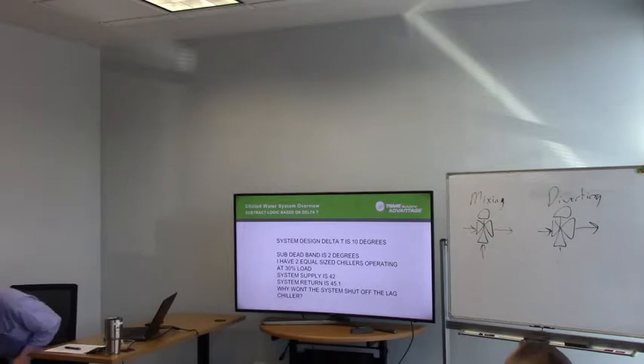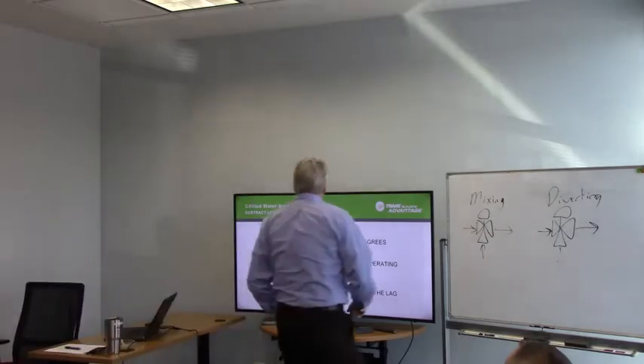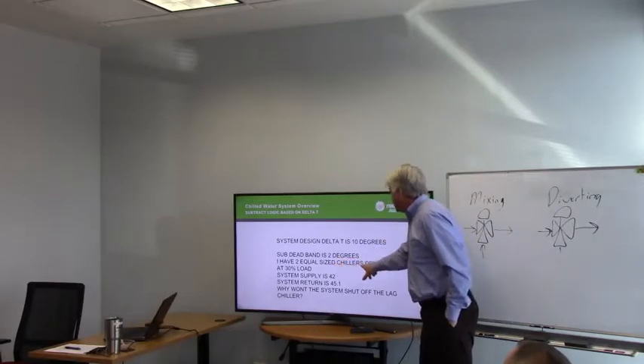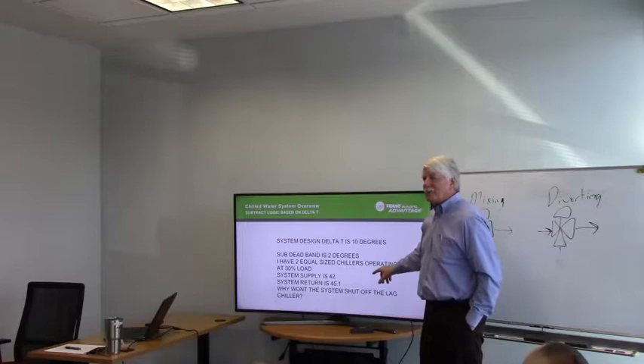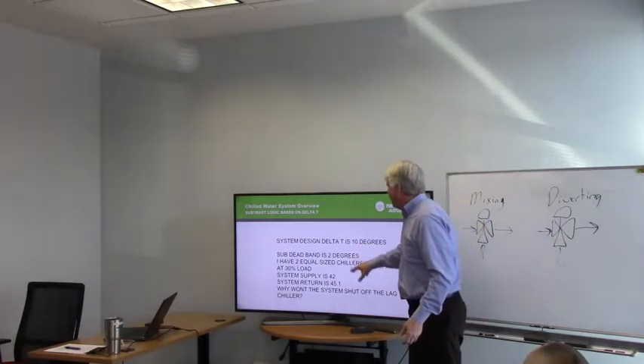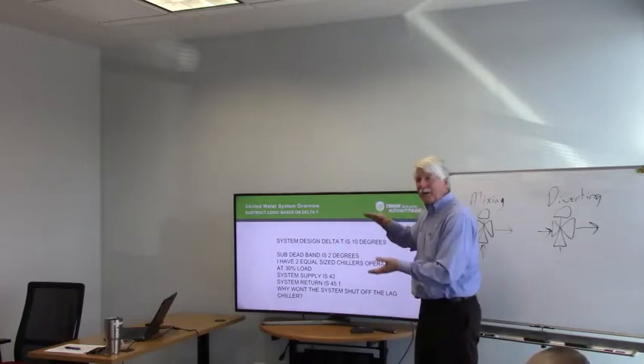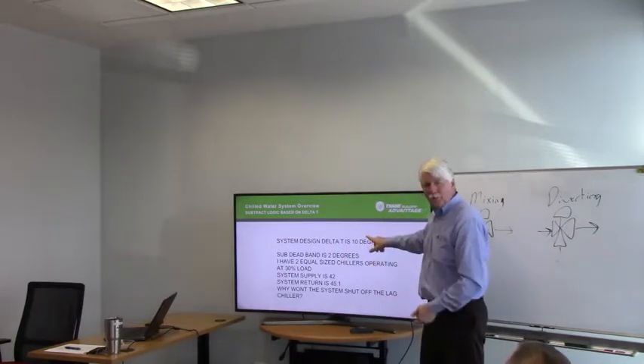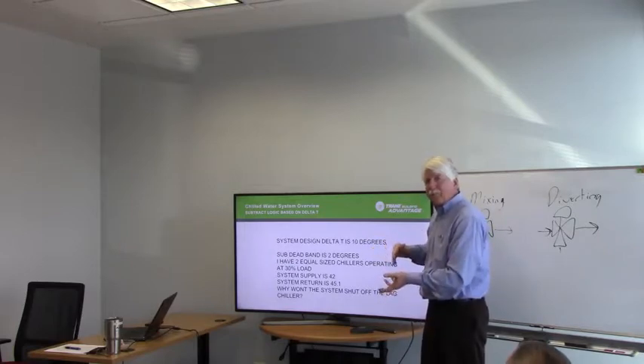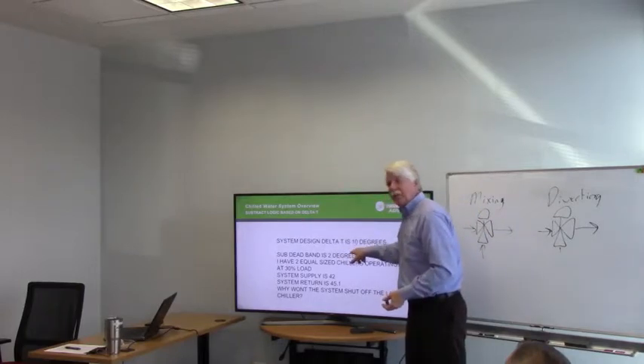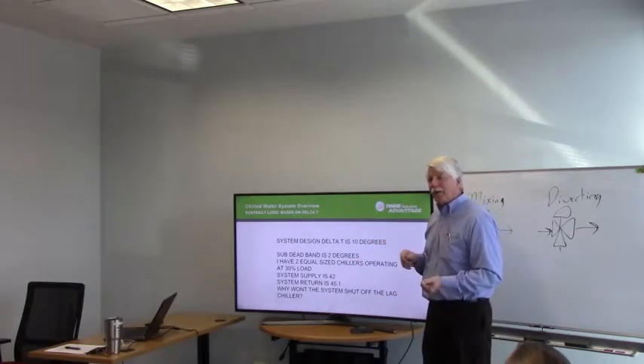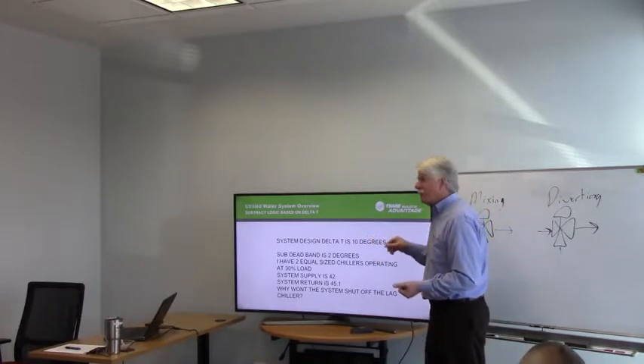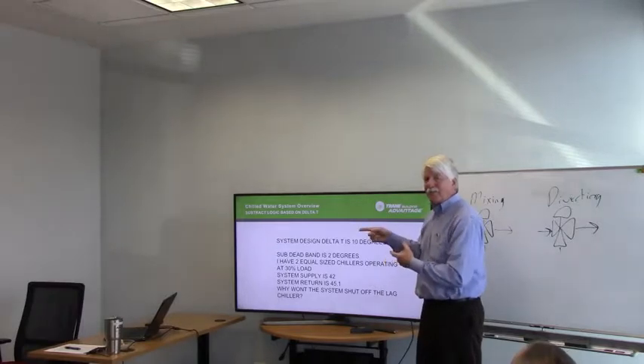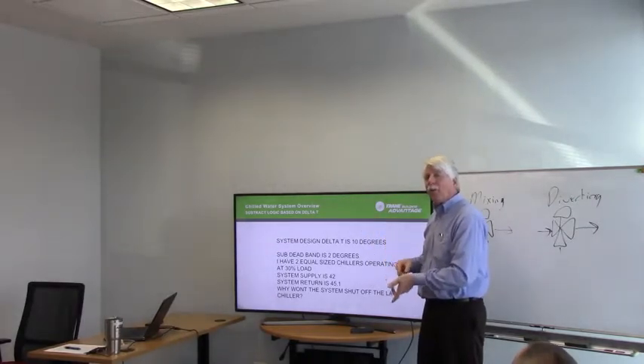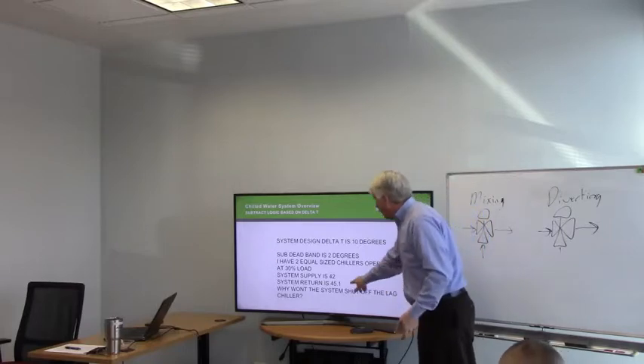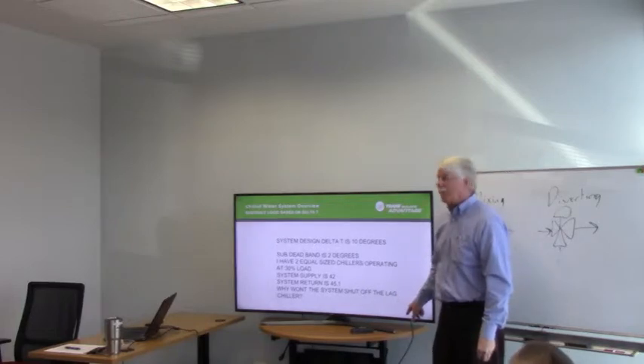The way that chiller plant control works is, first of all, it says I have equal size chillers. So that means theoretically, each chiller can do, of the total system work, 5 degrees worth of work. Because if 2 chillers are doing 10 degrees, 1 chiller can do 5 degrees. And we told it has a 2-degree deadband. Well, if 1 chiller can do 5 degrees, it looks at the return water and says, okay, the return water is 47 minus 2 degrees, it has to get below 45. So until we get below 45 degrees, it won't shut off a chiller.